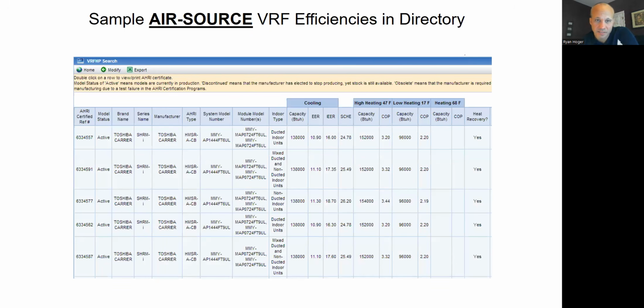So we have, I know you guys probably can't see this, EER, IEER over here, COP at 47, COP at 17, and then simultaneous in between, right? So in this example, the EER is 10.9, the IEER part load is 16. That's common for variable speed equipment to have a really good part load efficiency. Heating in this example was 3.2 at 47 degrees, 2.2 COP at 17, and then combined it was 24.7 if I'm running equal parts heating and cooling at that exact same moment. So most of the time I'll be operating somewhere between 10 and 25 for my EER.